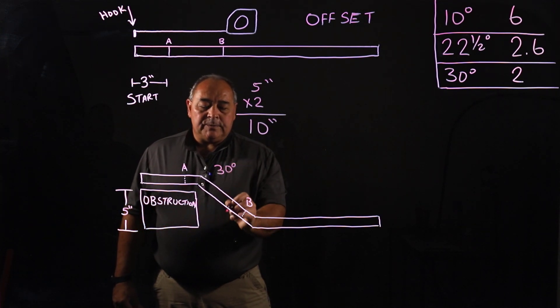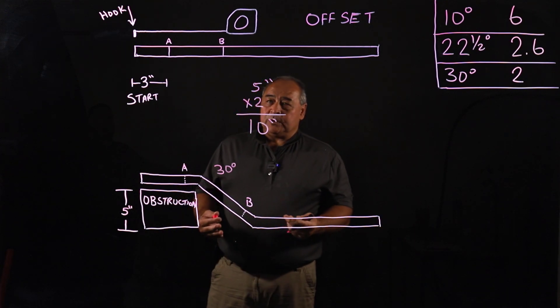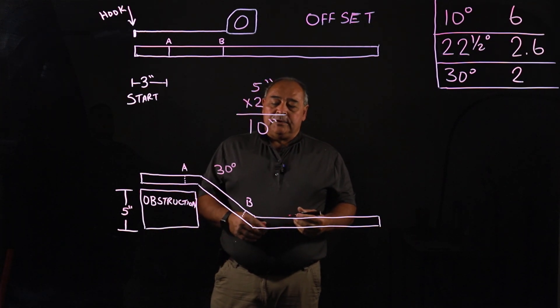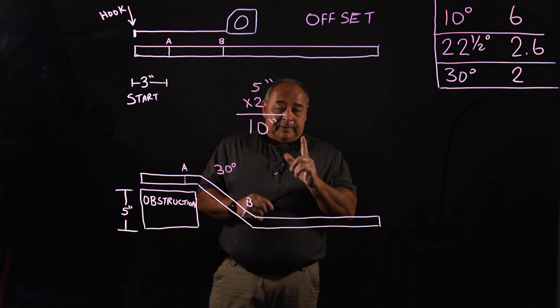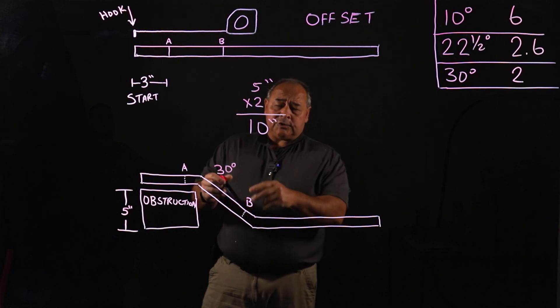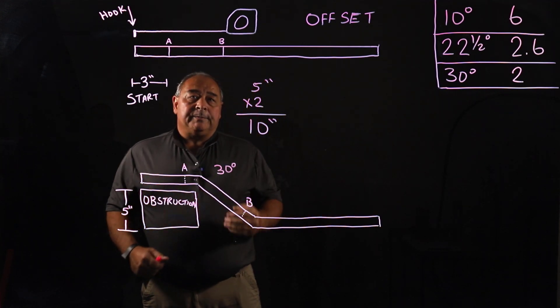So that's what I would choose and that's what I suggest that you guys would choose as well for a five inch offset, to use 30 degree bends. There's going to be two bends and there's two marks and they're opposite each other to make an offset.